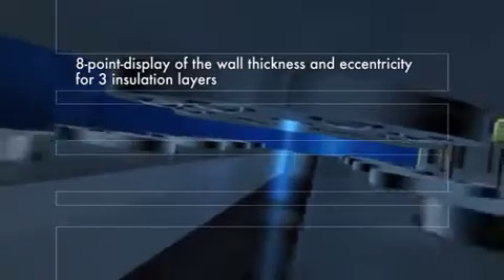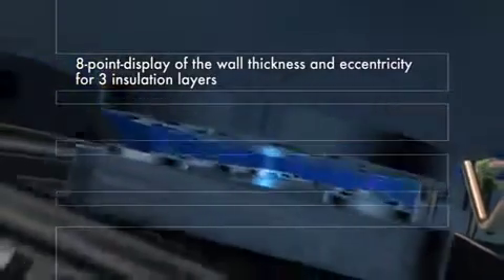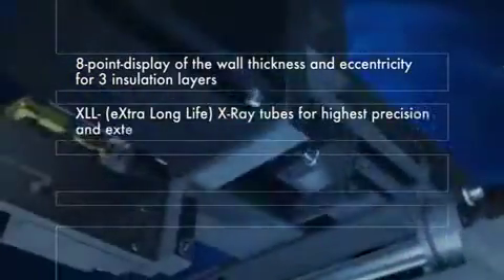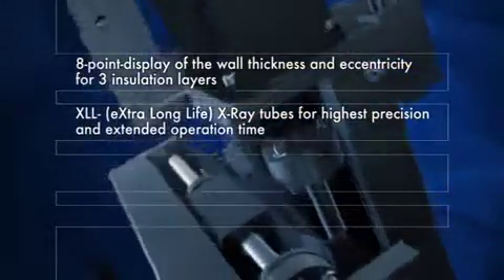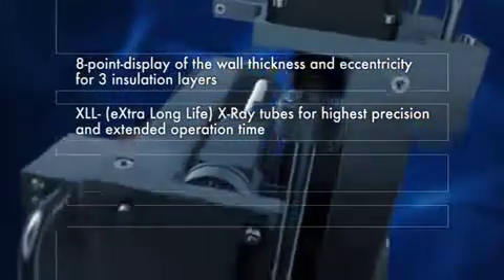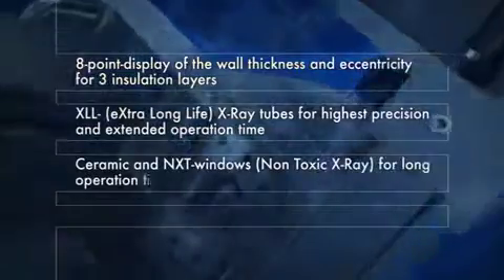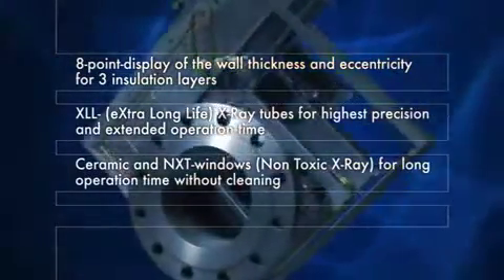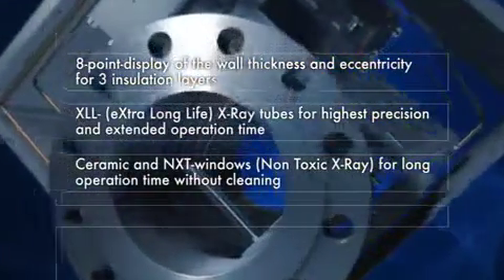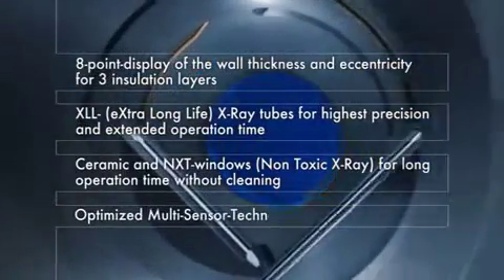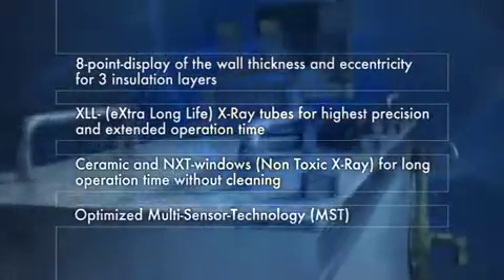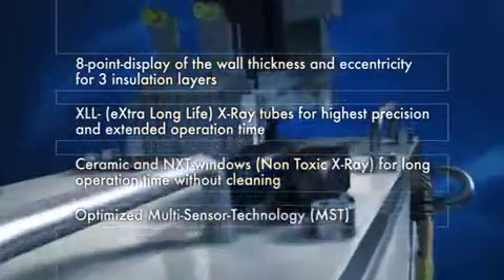8-point display of the wall thickness and eccentricity for 3 insulation layers. XLL Extra Long Life X-ray tubes for highest precision and life expectancy. Ceramic and NXT-windows, non-toxic X-ray for long-term operation without cleaning. Optimized multi-sensor technology for precise measurements, even at production-related cable vibrations.